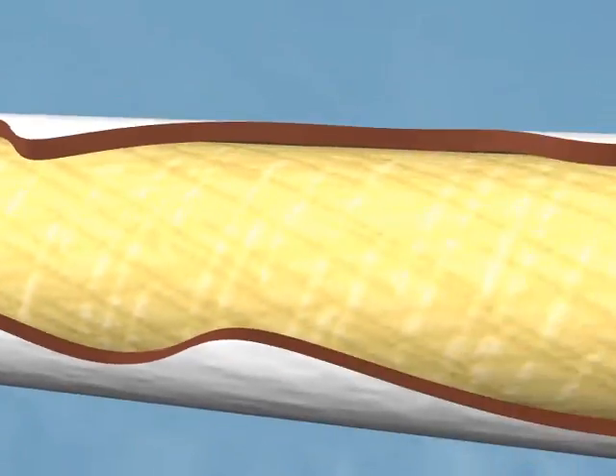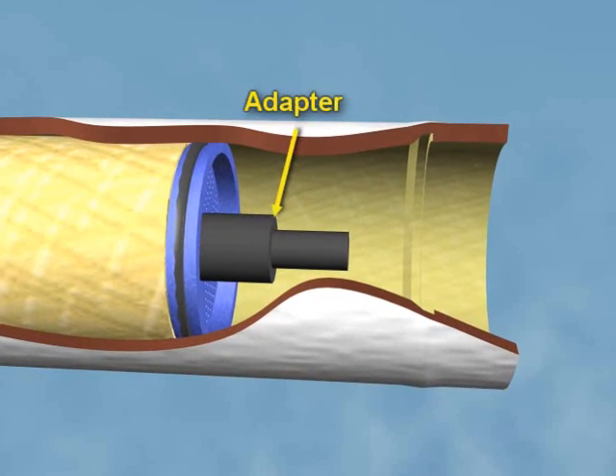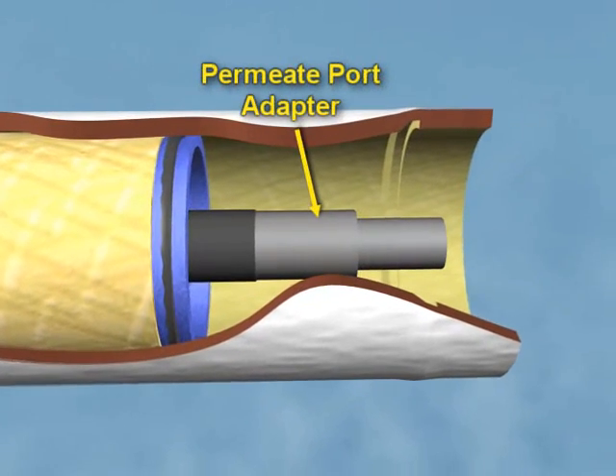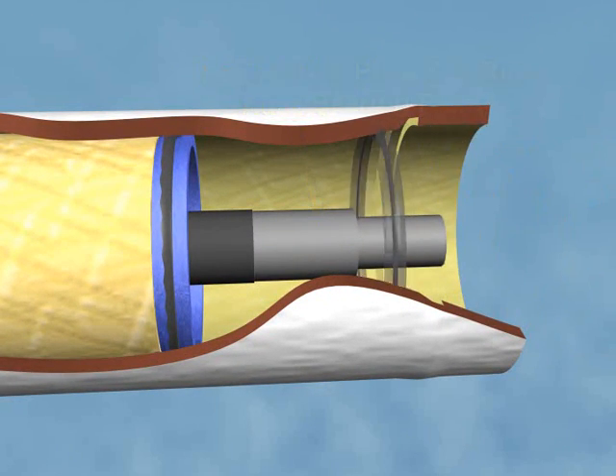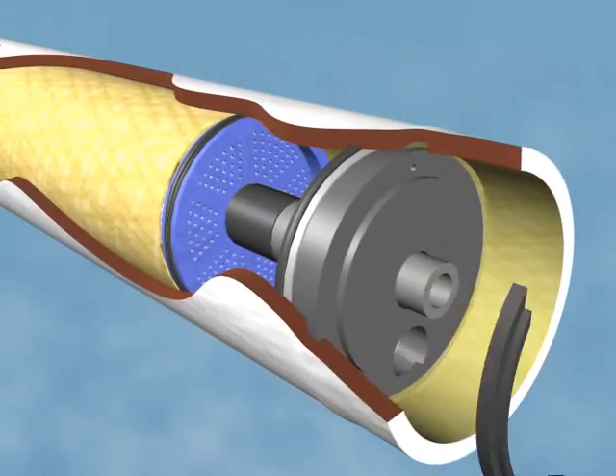Both the inlet and outlet side of the pressure vessel use an adapter. On the inlet side of the pressure vessel shown, an adapter with O-rings fits onto the product tube of the first element. The permeate port adapter fits onto the main adapter. A sealing plate with an O-ring and the bearing plate fit over the permeate port adapter.